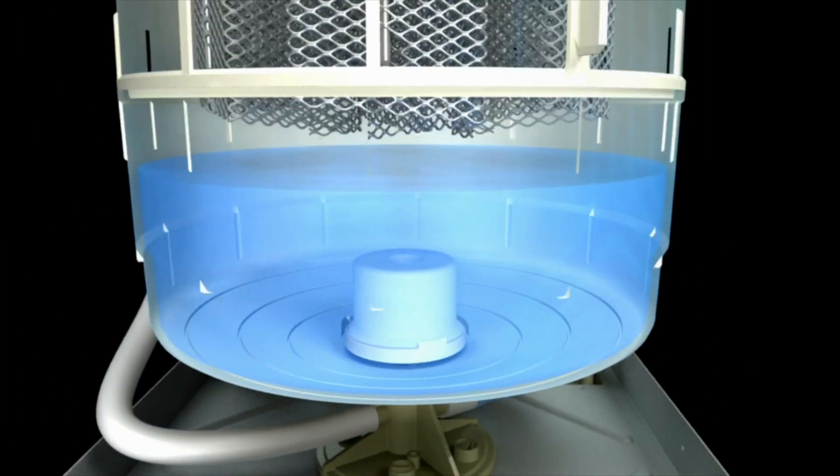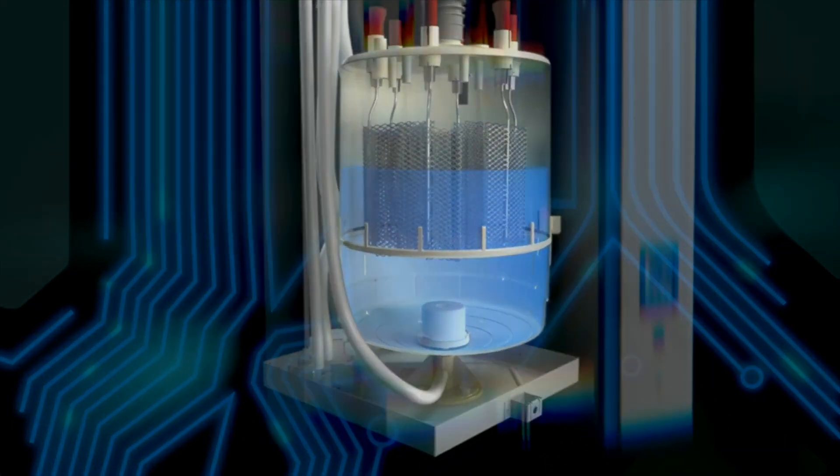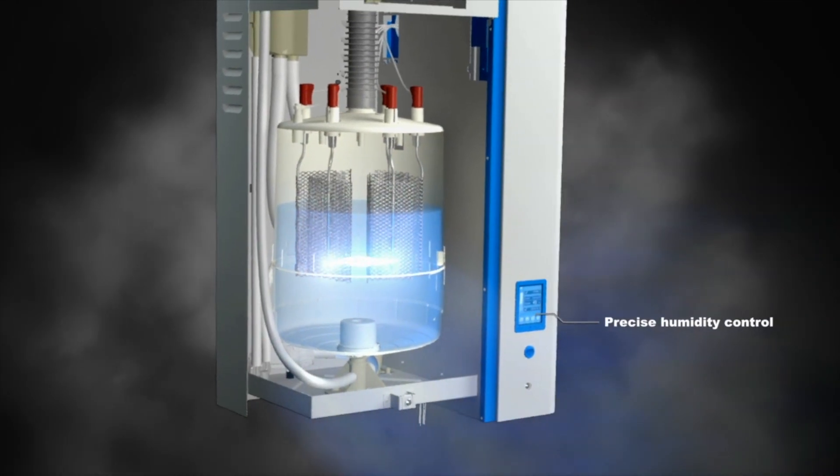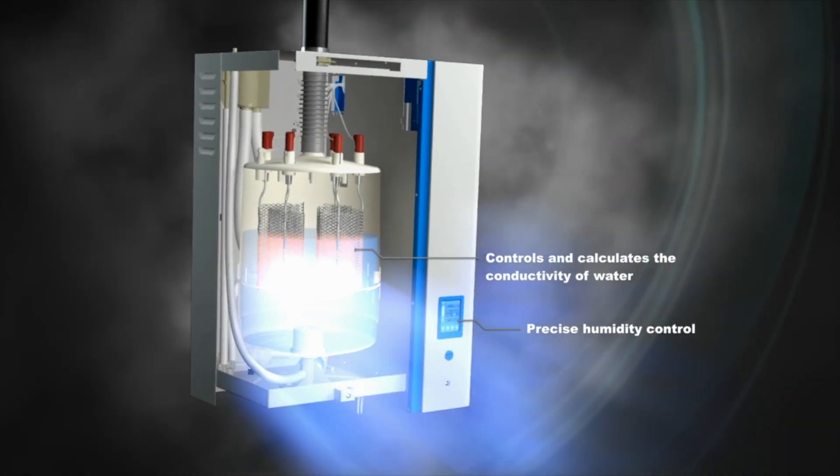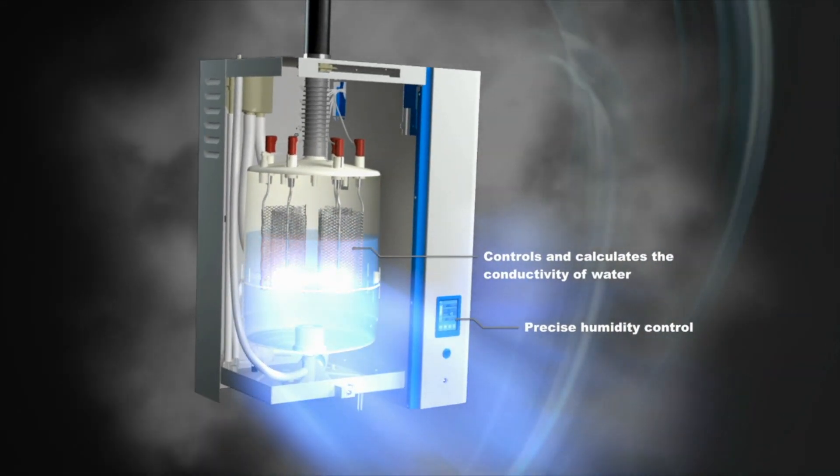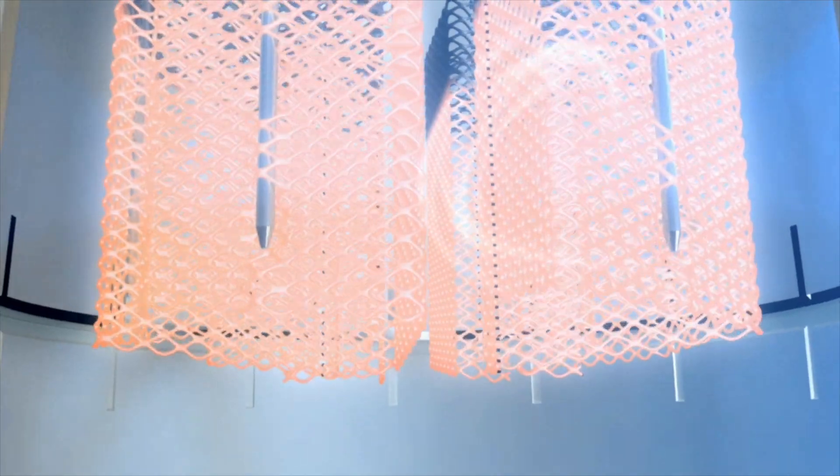Electric current flows through the water according to its conductivity. The controller routinely monitors the water conductivity and regulates steam production by optimizing water feed to the steam cylinder.